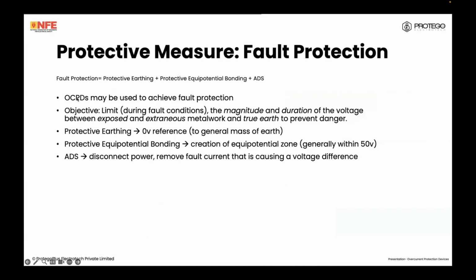This is what we in NFE, Mr. Gopakumar always hammers down, is that fault protection is protective earthing plus protective equipotential bonding plus automatic disconnection of supply through the OCPD or RCD for TTs. OCPDs are used to achieve fault protection, but they only achieve the ADS. These two have to still be there, protective earthing and protective equipotential bonding. That's only when you are achieving fault protection.